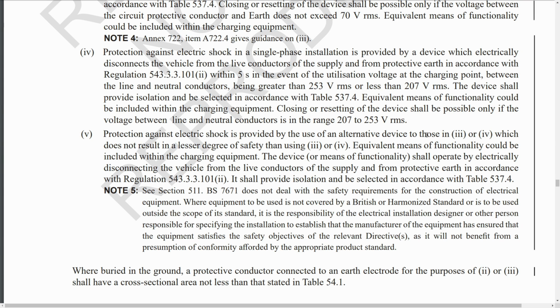And of course the problem there is that someone standing on the earth outside with a lead in their hand or touching the car could get a fatal electric shock. Now, there is a problem with this particular item here in that it is possible for a broken PEN conductor to occur and the voltage between line and neutral remains within this range, but the voltage between either line and neutral to the actual earth outside is greater than 70 volts.